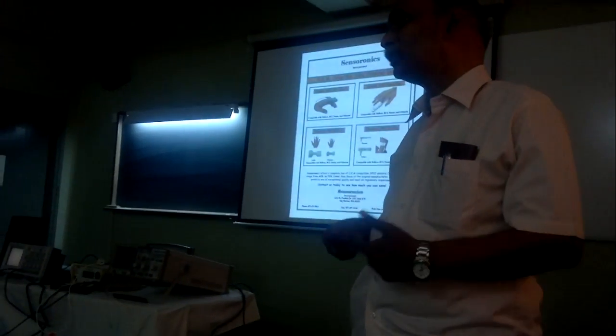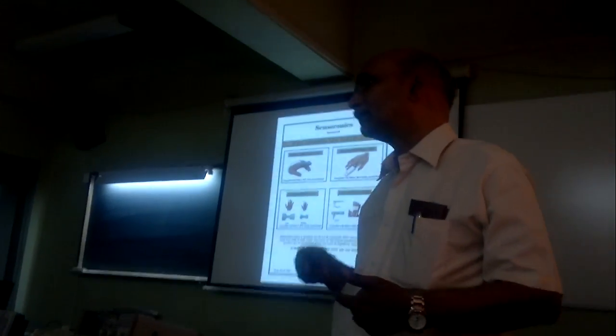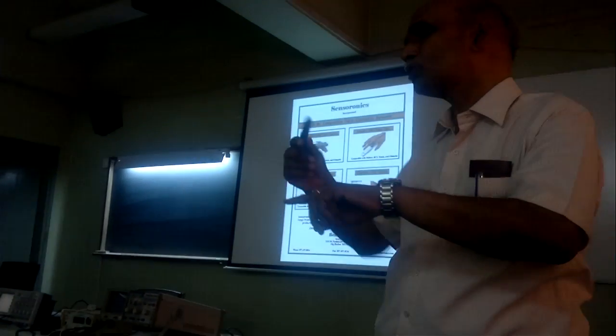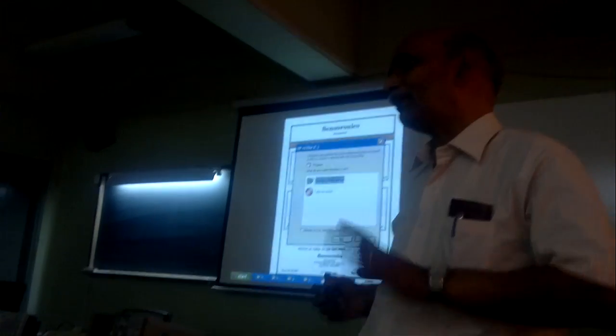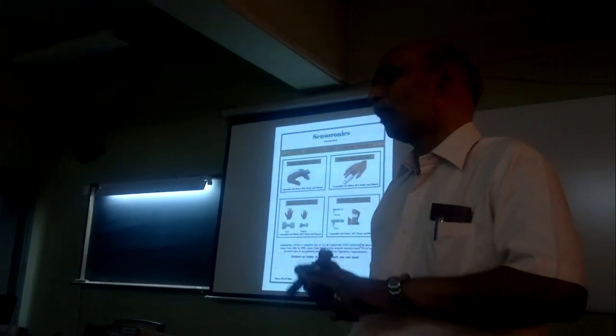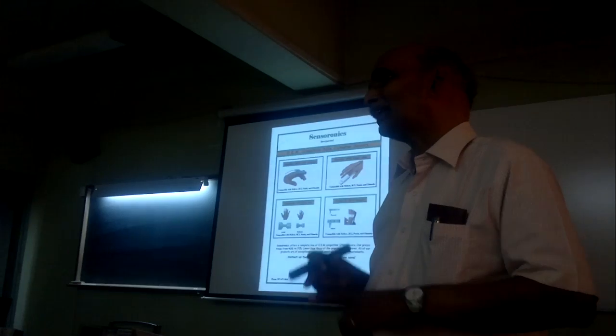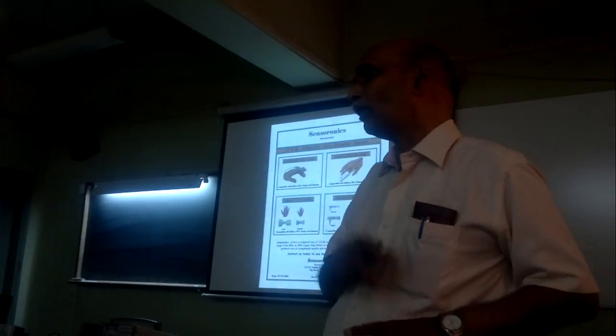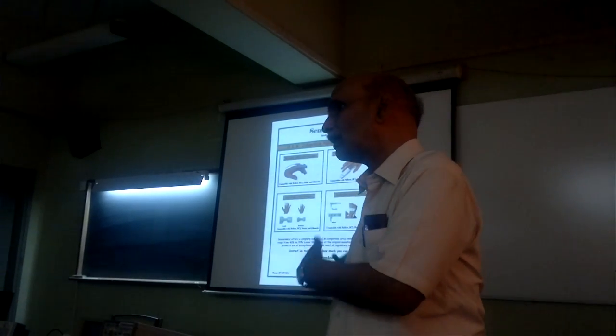Now pulse oximetry can be done in two ways. One is called the transmission method, where the light passes through the fingertip and is received on the other side. The two wavelengths used are red and infrared, and the detector is common. You have only red or infrared at a time, not both. Either it's the red or the infrared, and that's how you detect.